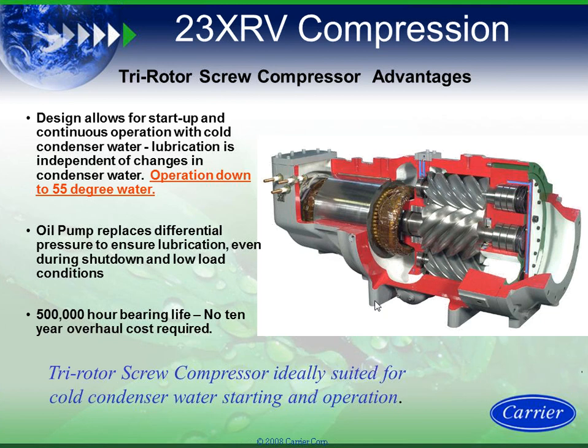Again, we're looking at the machine. It's different than typical screws because I can actually operate it with cold condenser water. It's got its own independent oil distribution system, so I can now basically pump oil to the bearings, and I can operate this machine down to 55-degree tower water. And as I mentioned before, it has 500,000 hour bearing life. No 10-year or 20-year overhaul cost required of an owner.